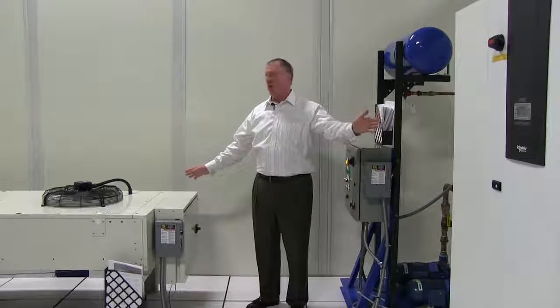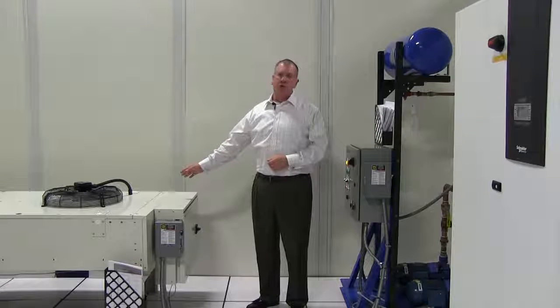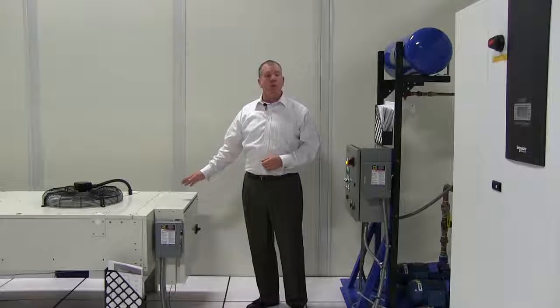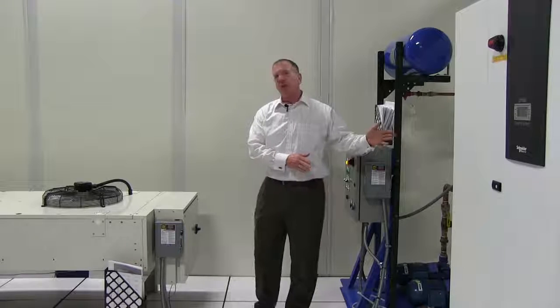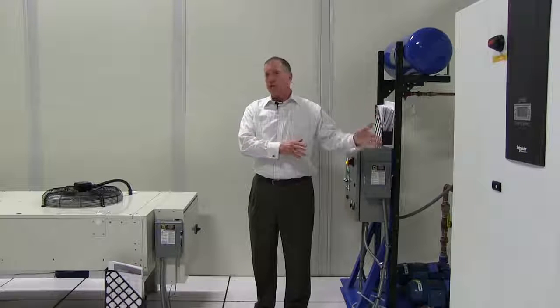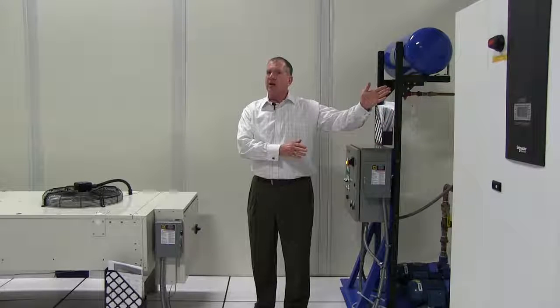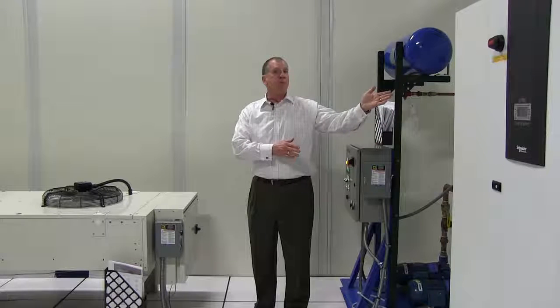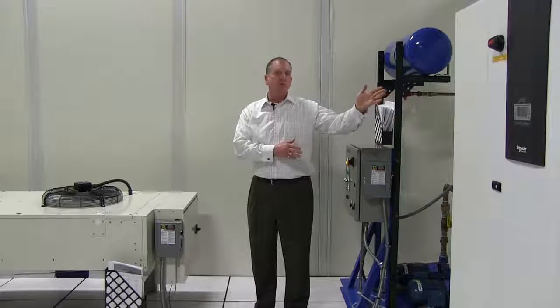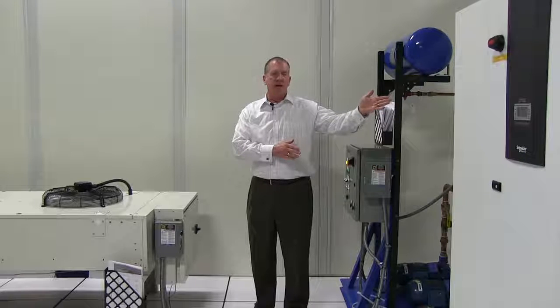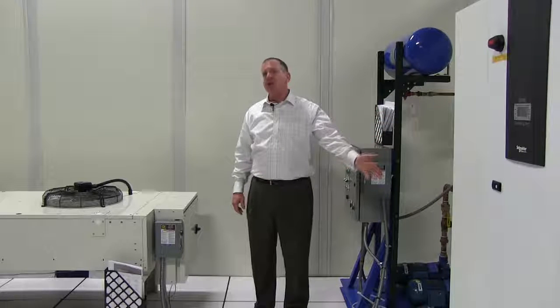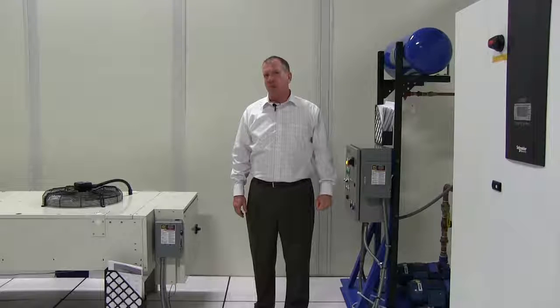so that whenever the return air temperature and the outdoor ambient had a 16 degree or greater difference, the dry cooler would default to winter mode. At that point, an indoor temperature sensor comparative signal would measure that the glycol was sufficiently cold enough to divert flow to the economizer coil. At that point, the unit has the ability to do either partial or full economization. Partial economization is supplemented with the DX compressorized cooling.